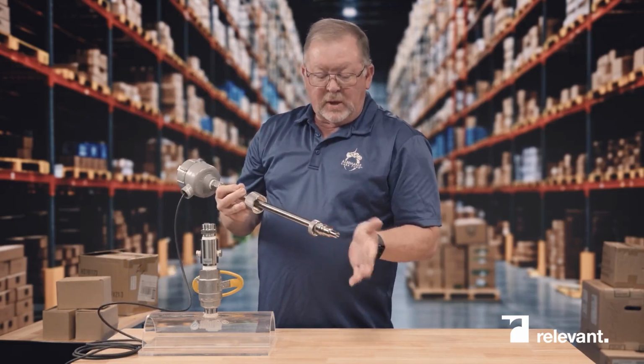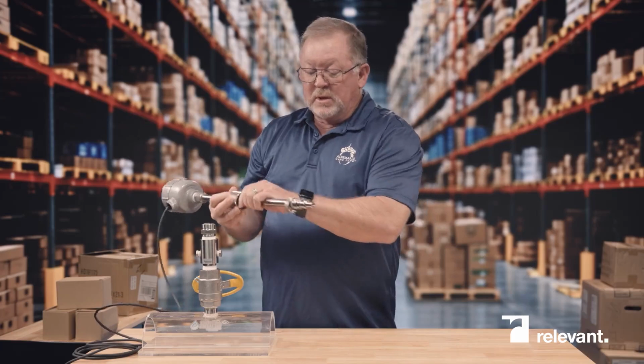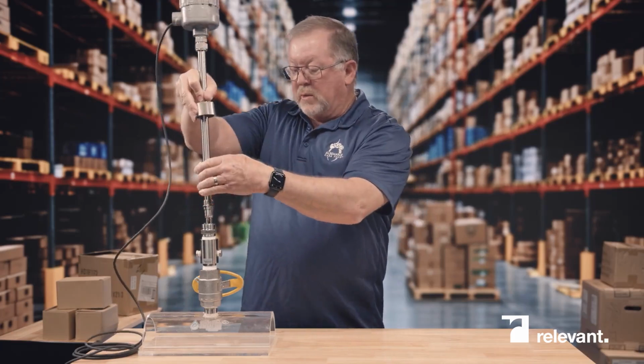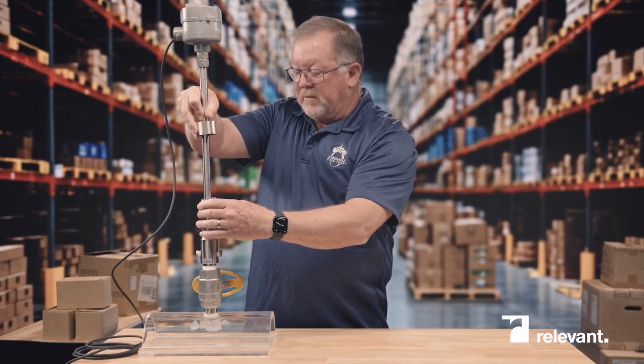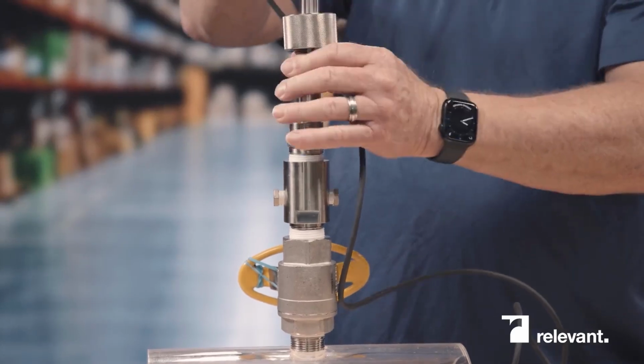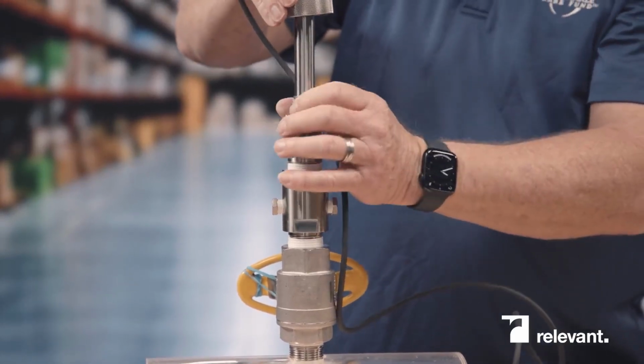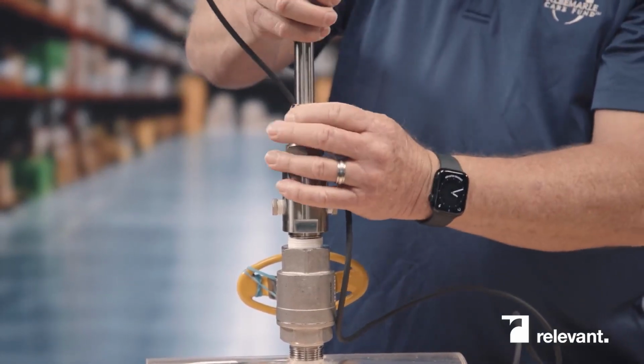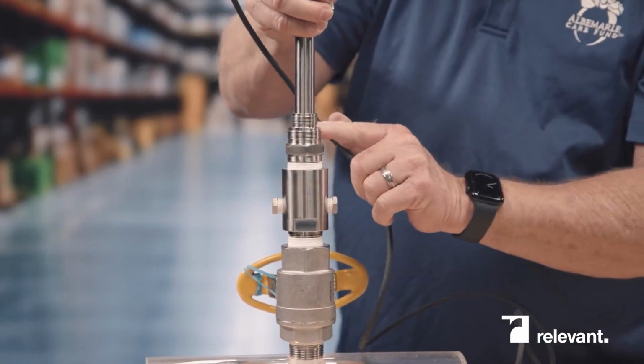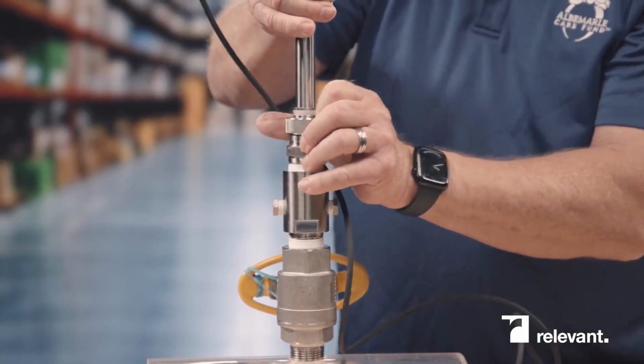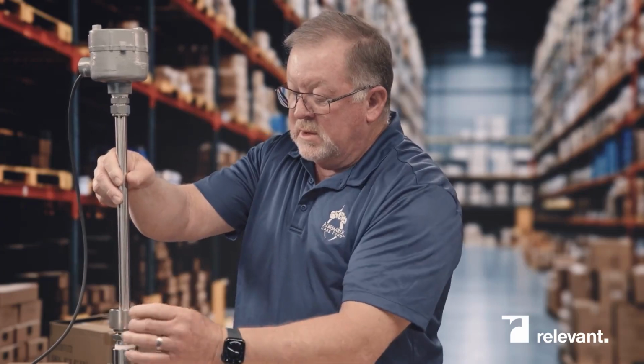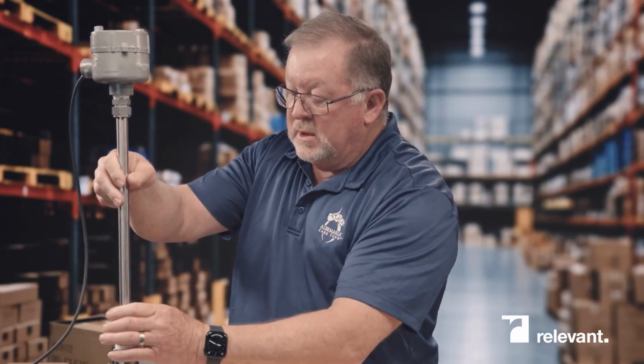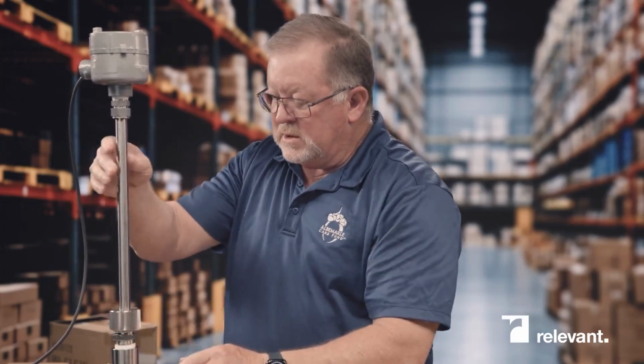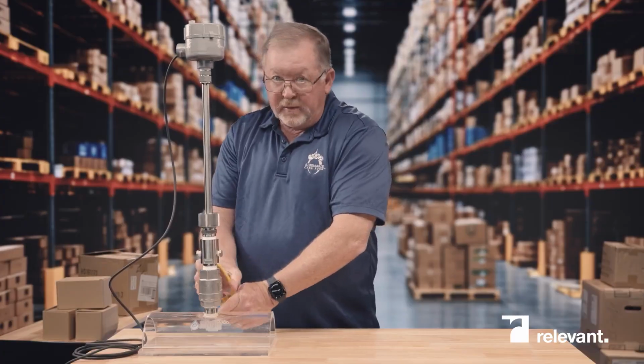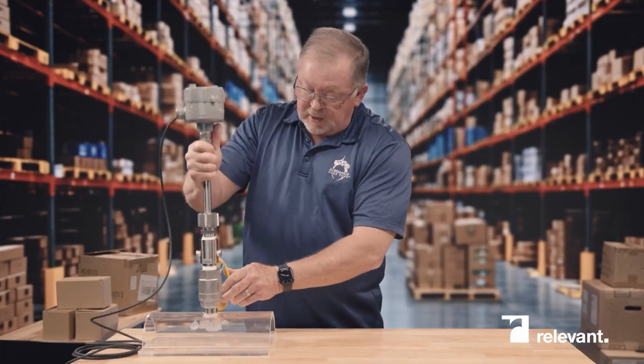Once that is okayed, the electrode is still good, you reverse the process by reinstalling it into the locking fitting, aligning the flats, reinstall this nut hand tight, no wrenches required. Once that is complete, slide the knurled nut down, finger tight so you can still adjust, open the valve, reinsert, and you're back in business.